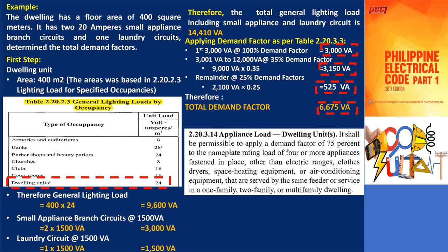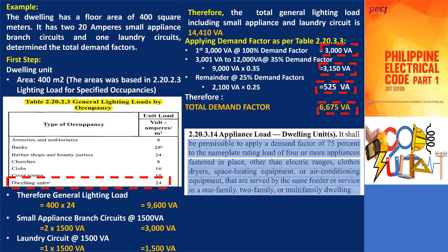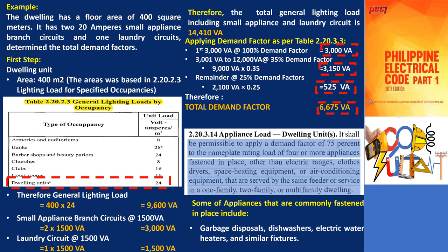To continue for other appliances, we can refer to section 2.20.3.14 of the electrical code — appliance load, dwelling units. According to this section, a demand factor of 75% can be applied to the nameplate rating load of 4 or more appliances that are securely fastened in place. This rule applies to appliances other than electric ranges, clothes dryers, space heating equipment, or air conditioning equipment. It is applicable in one-family, two-family, or multi-family dwellings where these appliances are served by the same feeder or service. Examples of fastened-in-place appliances include garbage disposals, dishwashers, electric water heaters, and similar fixtures.